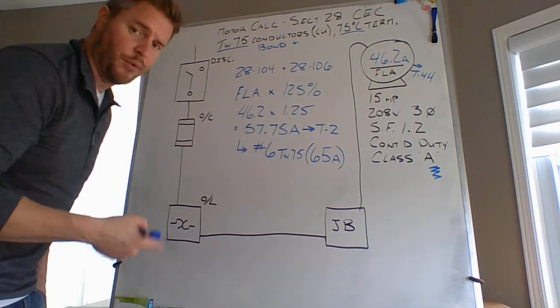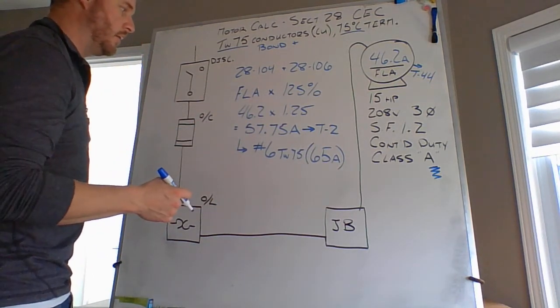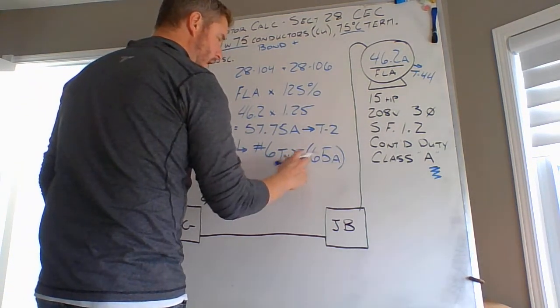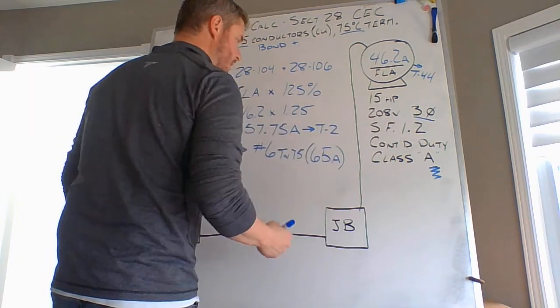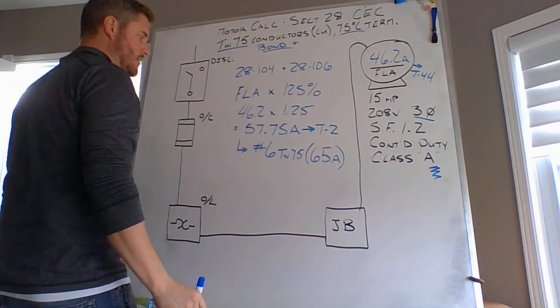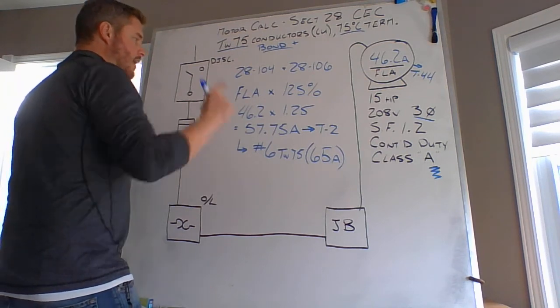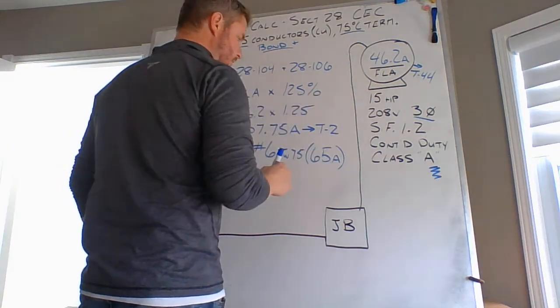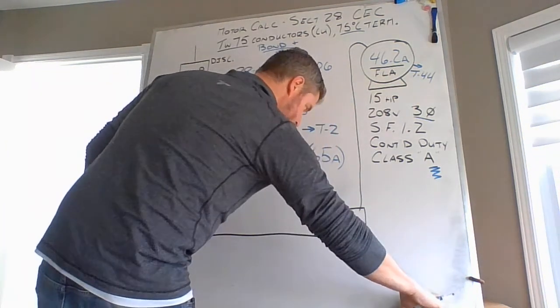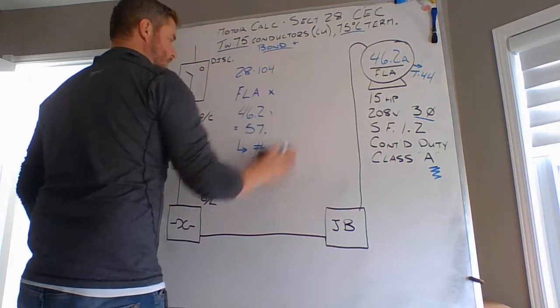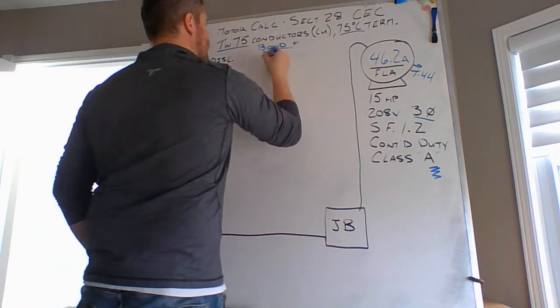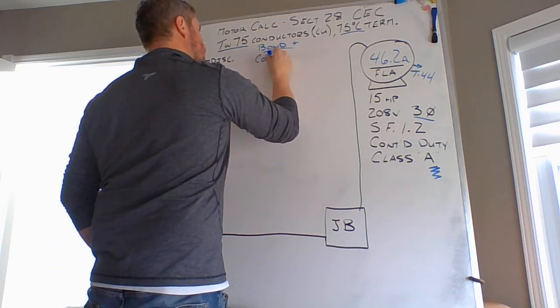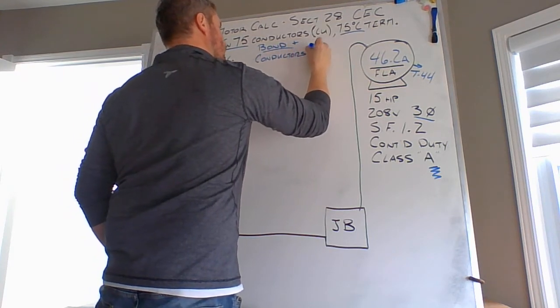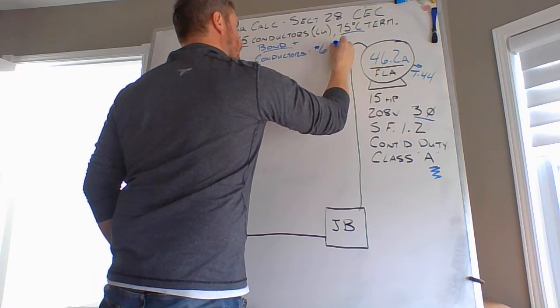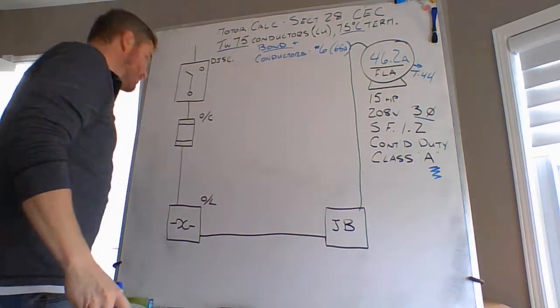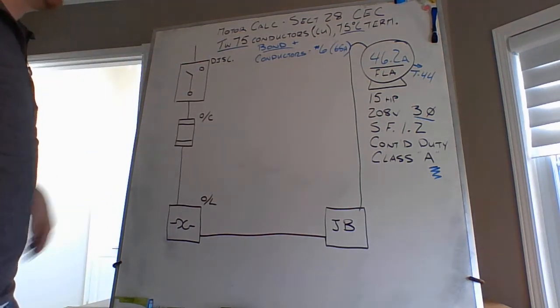But we'll talk about the expansion of the rule in just a minute when we start looking at that Class A thing. So in this case, number 6, TW75, I need a red, a black, and a blue. This is a 3-phase motor, and I'm also going to incorporate a bond into this. That's sizing my conductors to feed this motor. Check mark. We're good to go. I will record that up here. Number 6, good for 65 amps, TW75 insulation on those conductors.